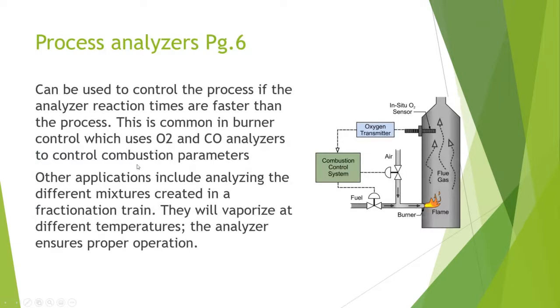The second application is process analyzers. Gas analyzers can be used to control the process. The key requirement is that the reaction time of the analyzer has to be faster than the process — it must react to changes quickly enough to make a difference. A common application is burner control, measuring oxygen and carbon monoxide to control combustion parameters for efficiency and safety. Other applications include maintaining product quality in fractionation or distillation processes.